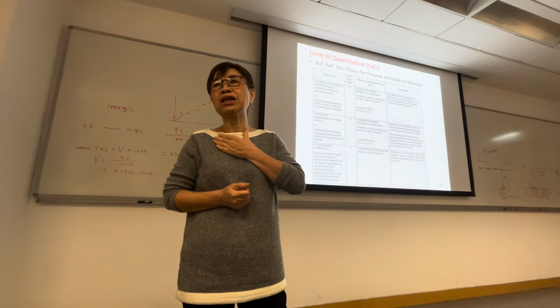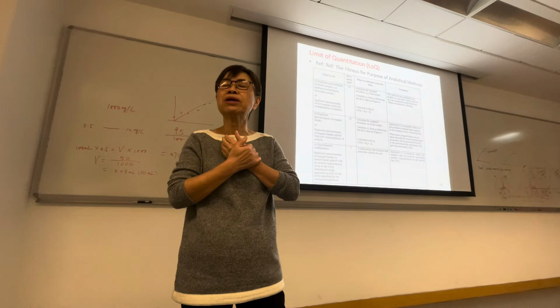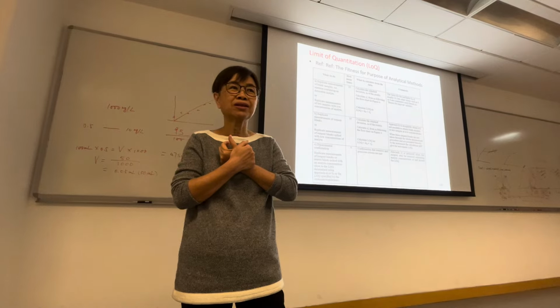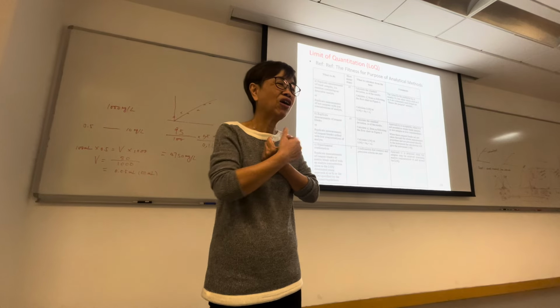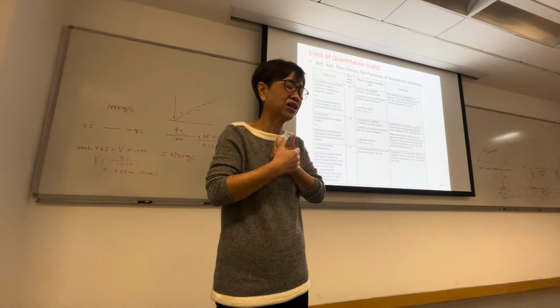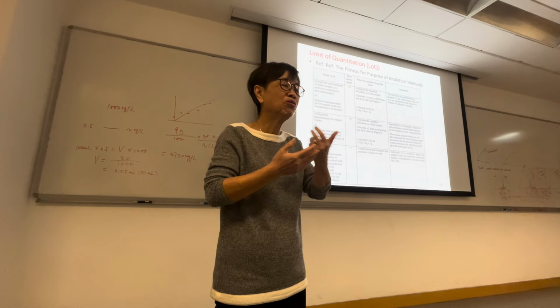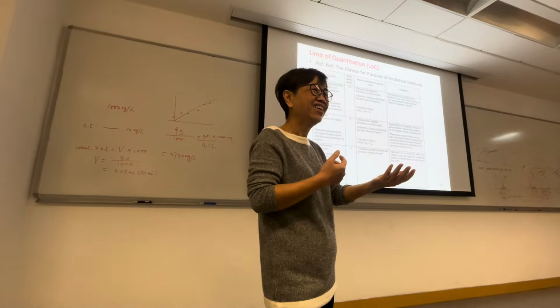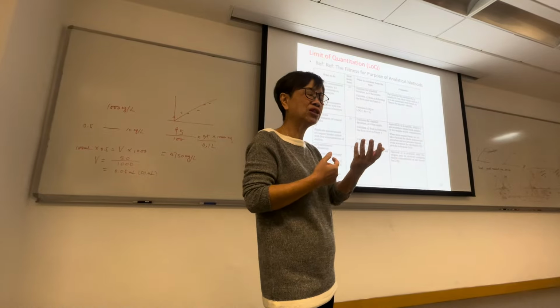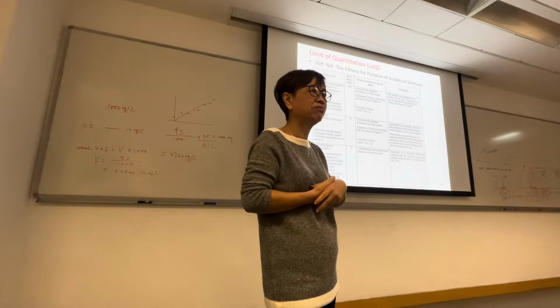But for LOD, once again, it depends on discipline. For environmental tests, you need to verify. But for other disciplines, we don't verify the LOD. Why don't we bother? We don't report any result below the LOQ.